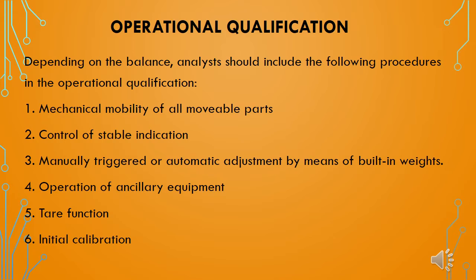Now we will see the requirements for operational qualification. Depending on the balance, the analyst should include the following procedures in the operational qualification test: first, mechanical mobility of all movable parts; second, control of stable indication; third, manually triggered or automatic adjustment by means of built-in weights; fourth, operation of ancillary equipment like printers; fifth, tare function; and sixth, initial calibration.